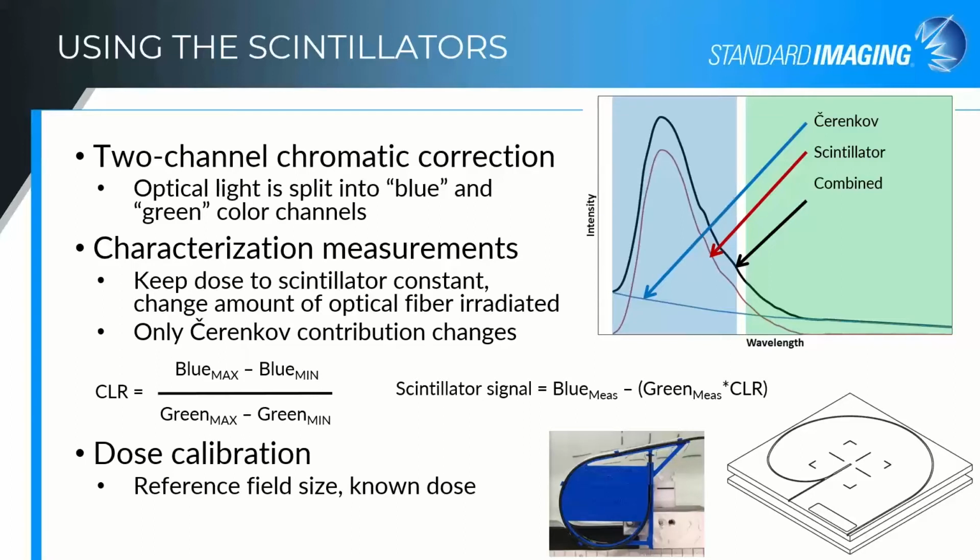There was a question that came up, I just noticed, about how do we change the length of the scintillator? That's in the construction. When we make the fiber, we either put a 1 millimeter piece of scintillation fiber at the end of the optical fiber, or a 3 millimeter long piece. It's a 1 millimeter diameter organic scintillator that we're cutting and polishing to be the right size.